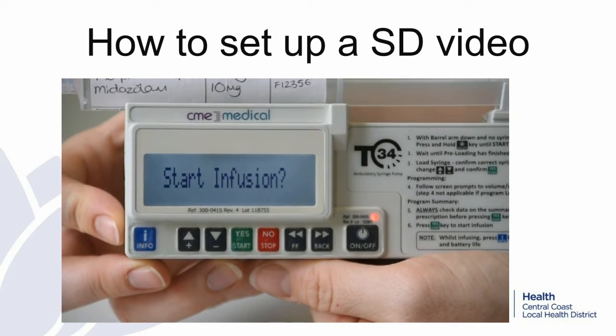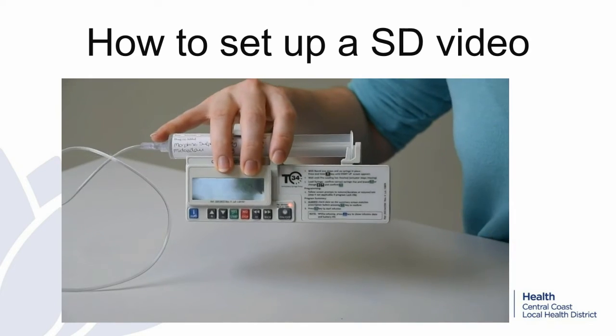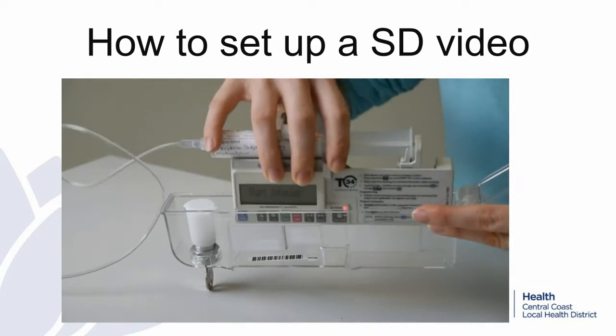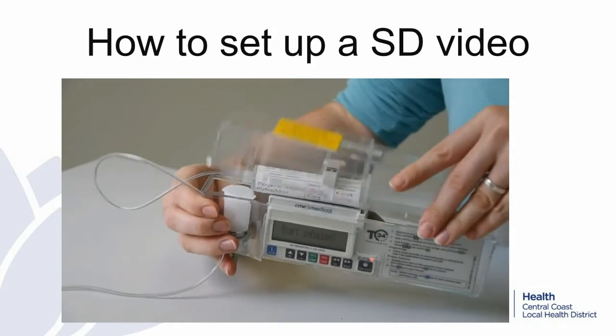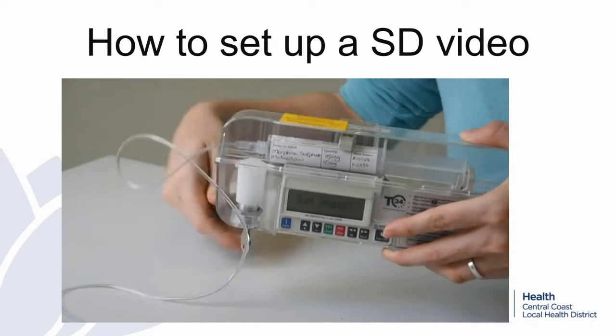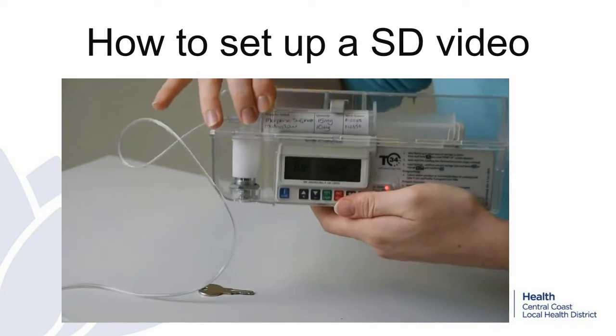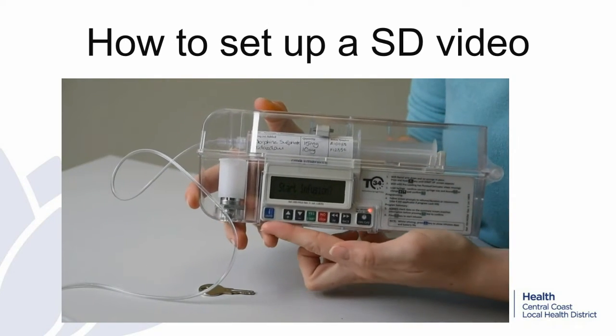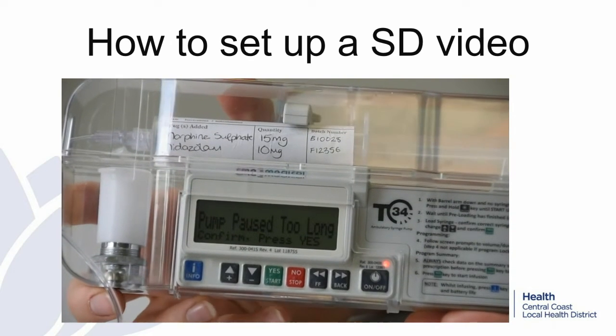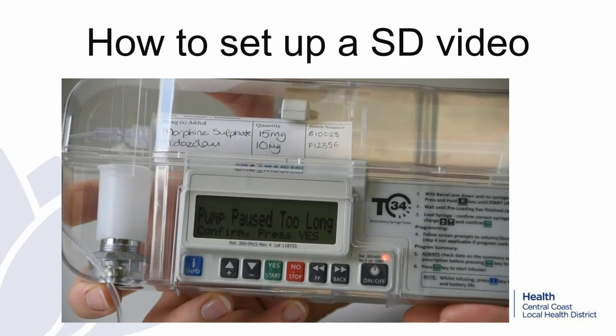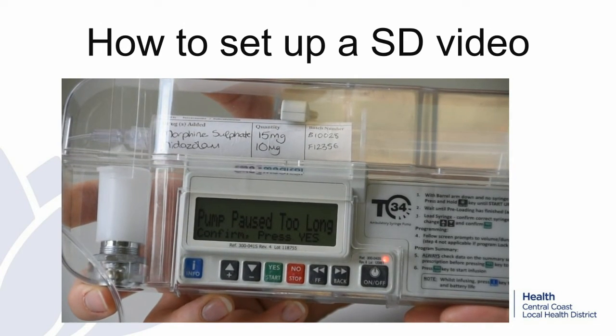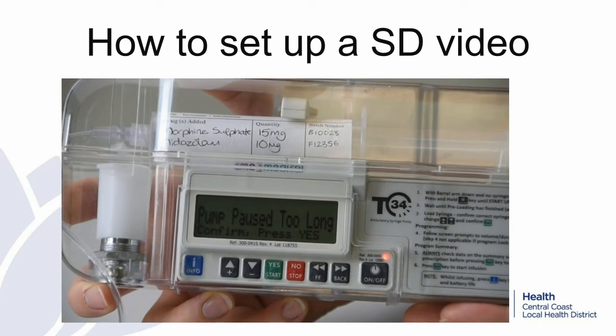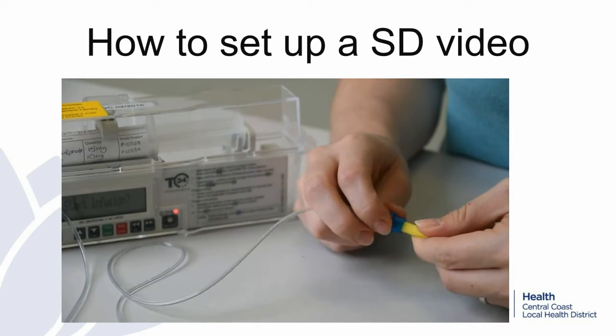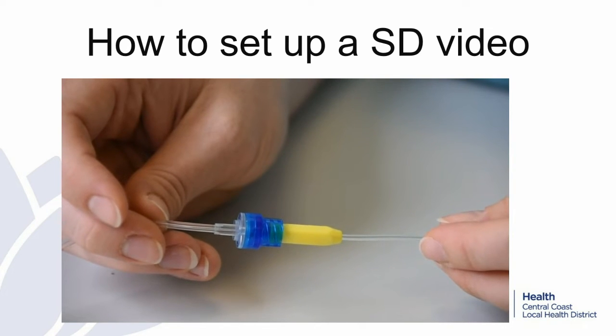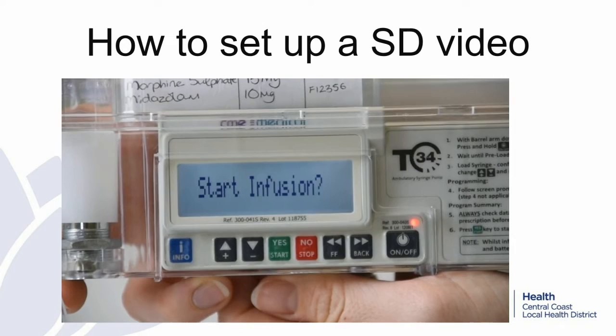Once ready to bring the pump to the patient, place the syringe pump into the locked box as shown and lock with the key. The control buttons will still be accessible with the locked box in place. You may see a pump pause too long message appear on the screen. The pump will alarm and the red light will come on. This is normal and it's simply an alert to make sure the pump is attended to. And once completing identity checks, bring the pump to the patient, connect line to patient. You can then start the infusion.